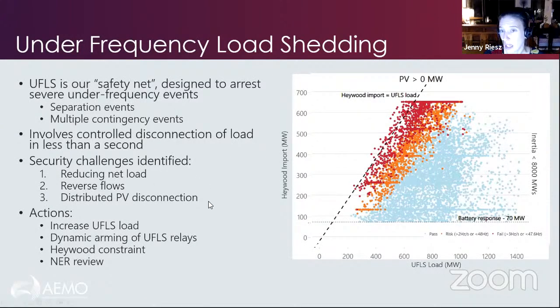So we've now reached the point in the South Australian region of our grid where we have periods with very, very little load on our under-frequency load shedding scheme, which essentially means that that safety net is now gone in those periods. We have nothing to arrest that frequency decline when it gets into those very severe disturbances.